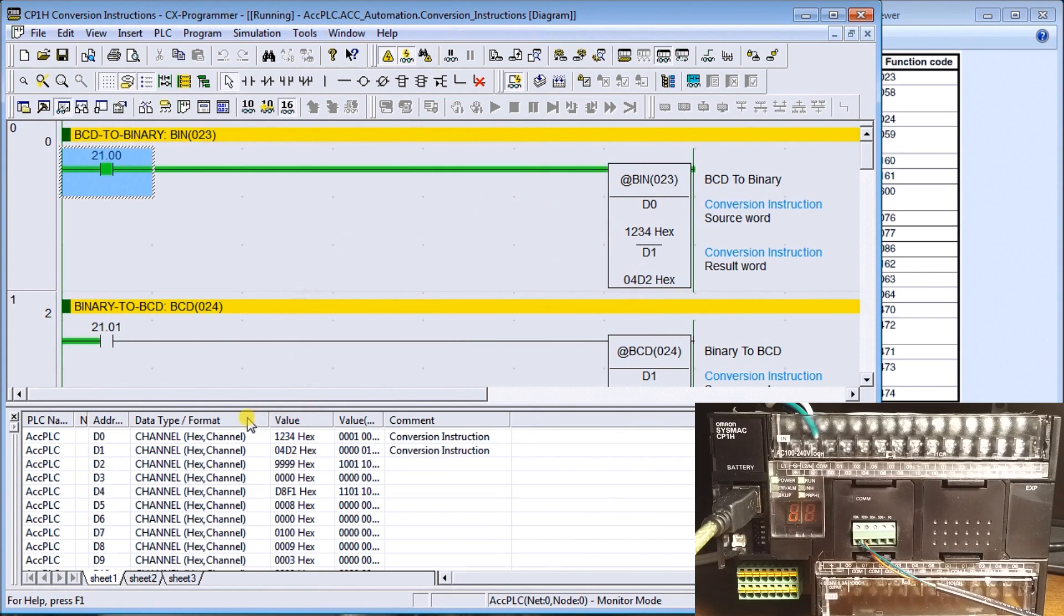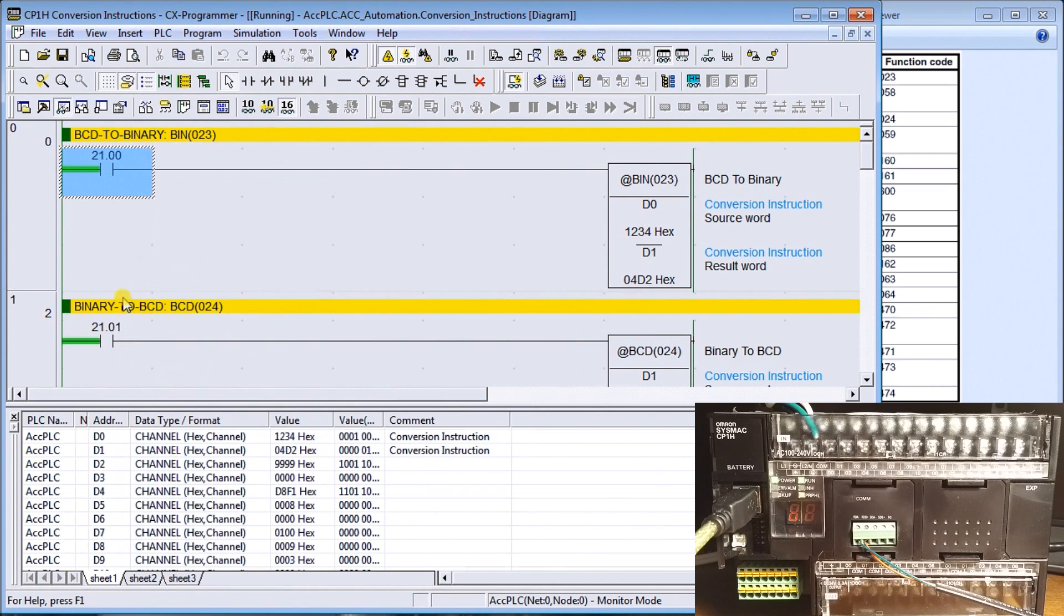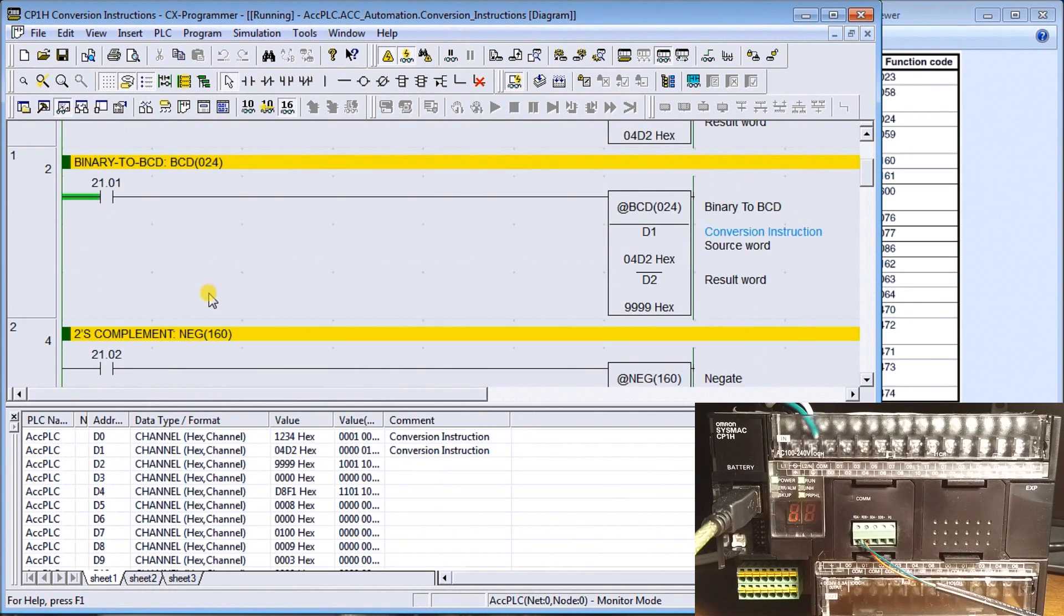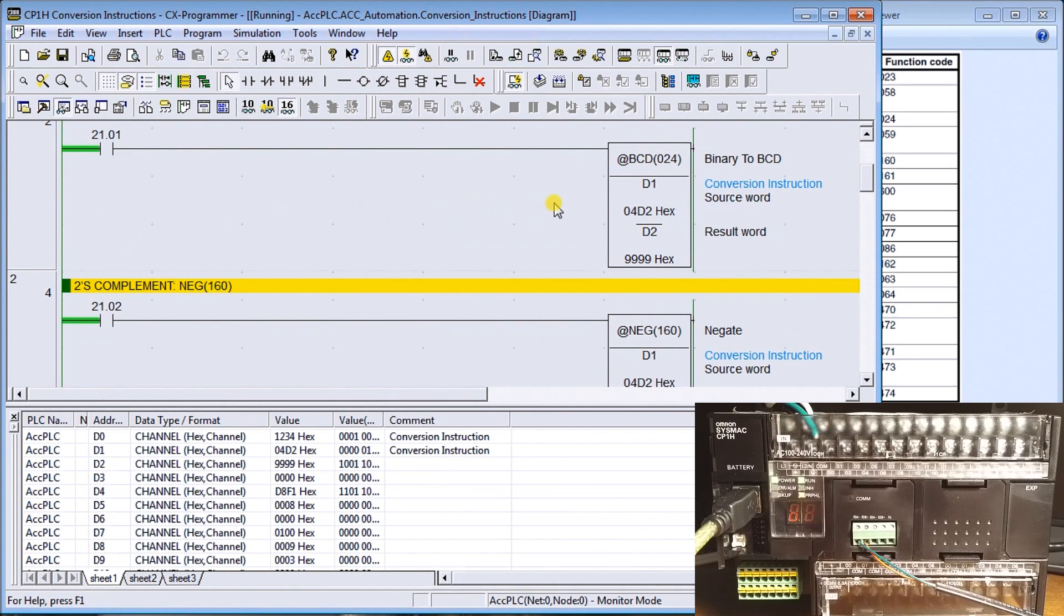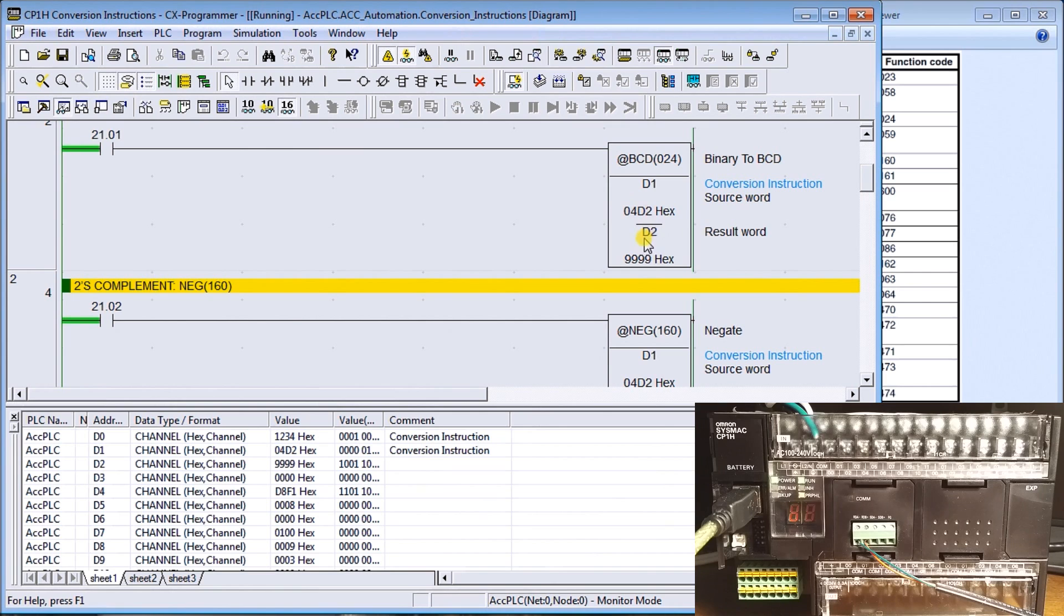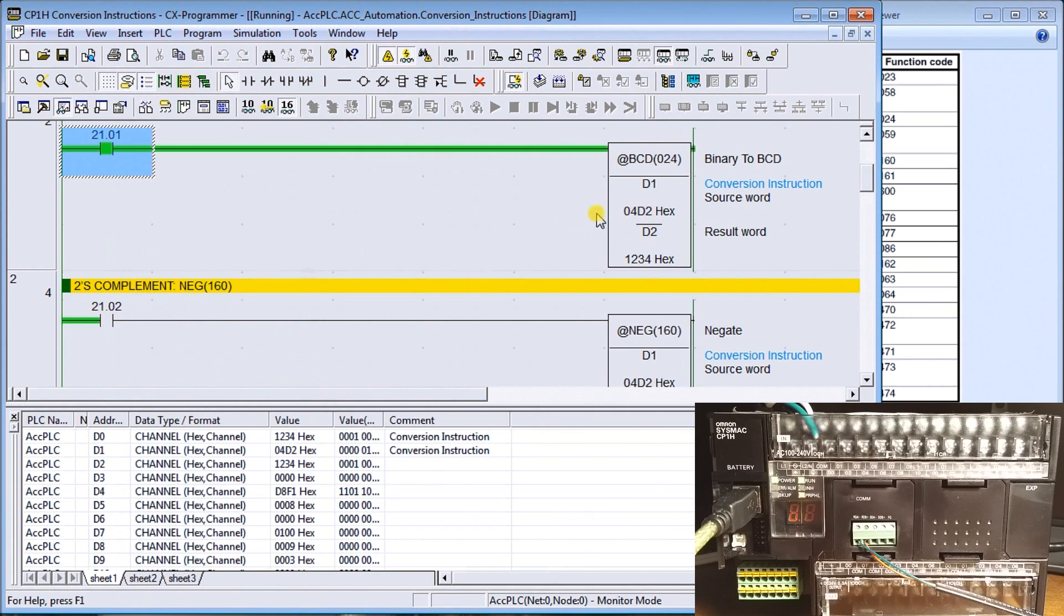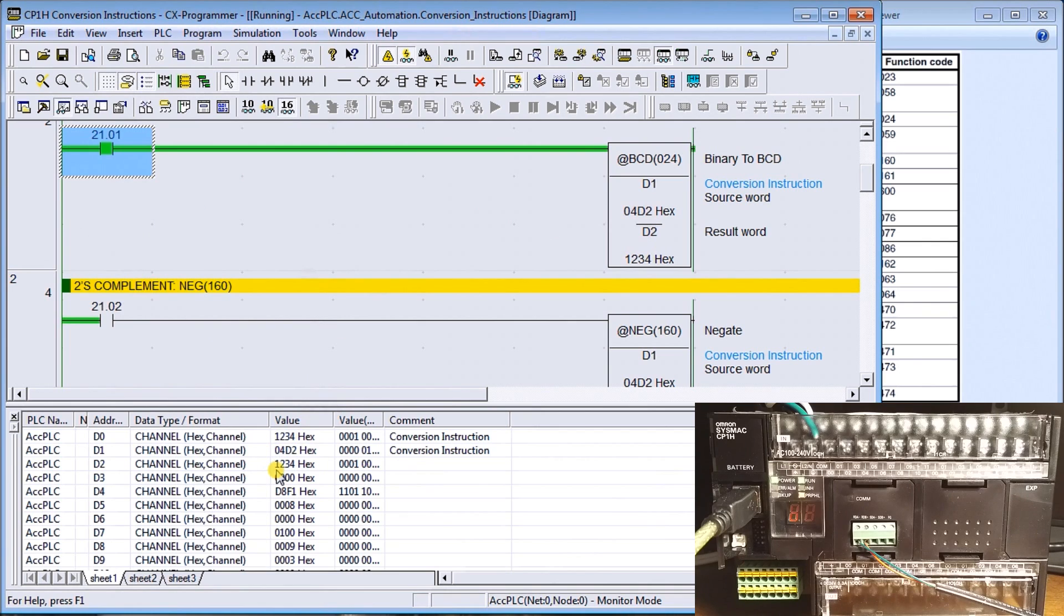That's my first instruction. The next one is binary to BCD. Here I have my binary and we'll use the same conversion we just did, 04D2. It will convert that into a BCD in data memory 2. So we'll turn that one on and sure enough, it turns to 1234 in channel 2, which is exactly what we expected.